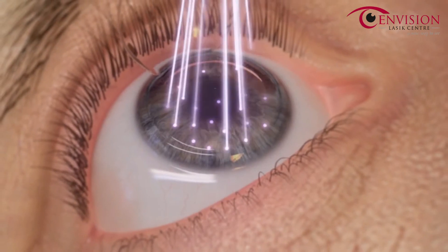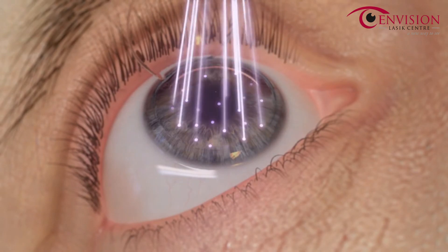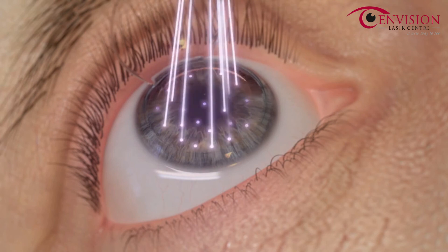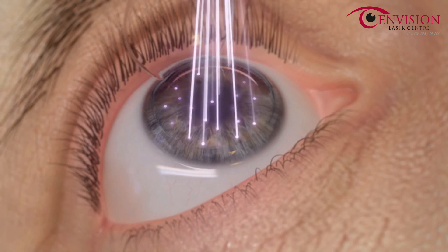This treatment algorithm provides a market-leading treatment rate of approximately 1.4 seconds per diopter. Designed to automatically track movements of the eye with a latency time of just two milliseconds, the WaveLight EX500 excimer laser sensor automatically adjusts pulse placement to provide patients with exceptional outcomes.